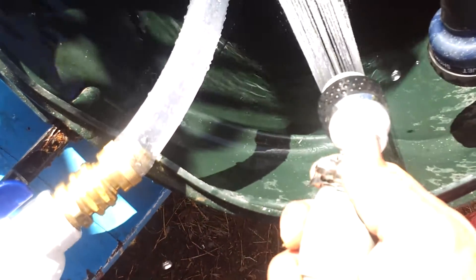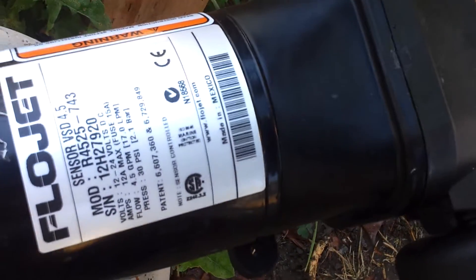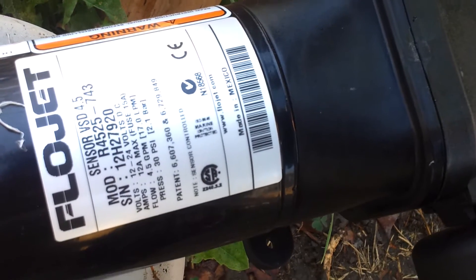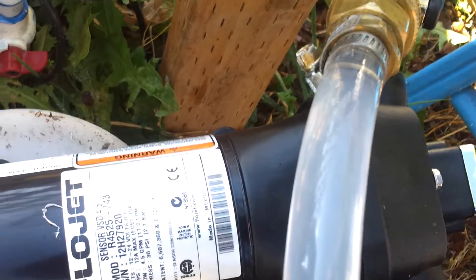We're using a lot of demand right now. I'm going to turn this off slowly. You hear it? Still running. I'll close it a little bit more, a little more. So this is variable speed — when the demand increases, the pump speed increases.